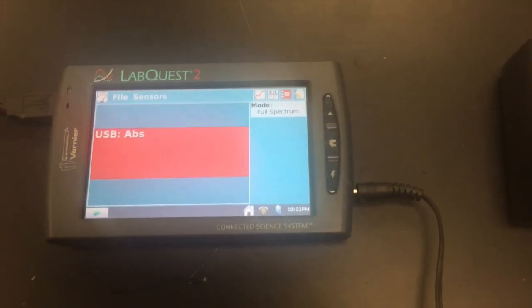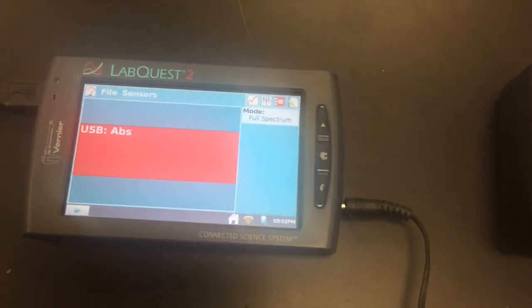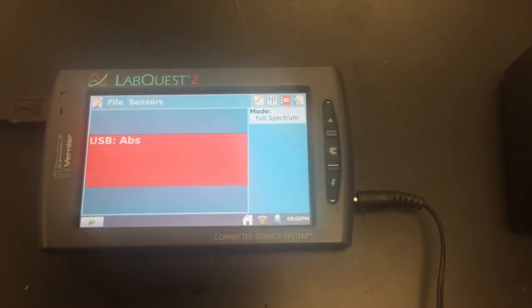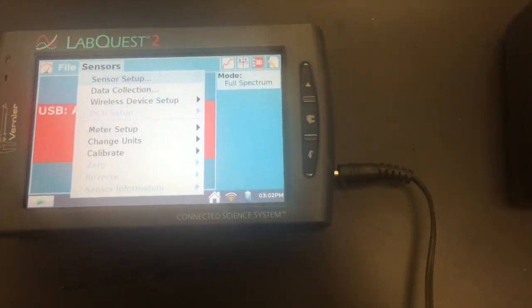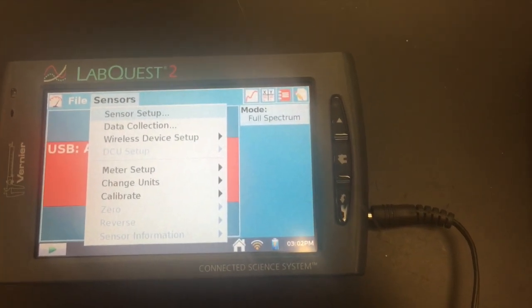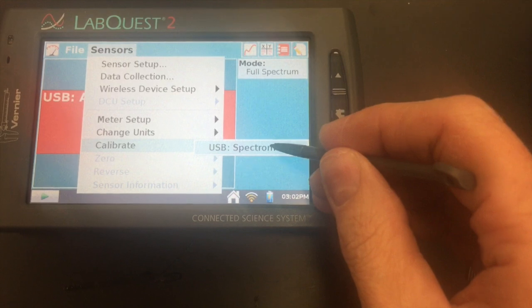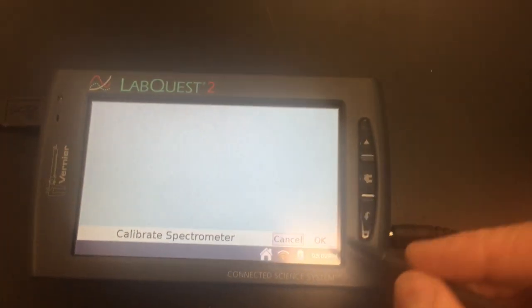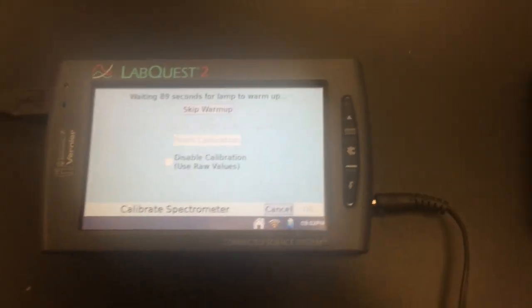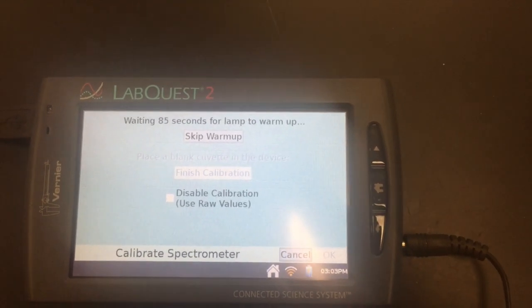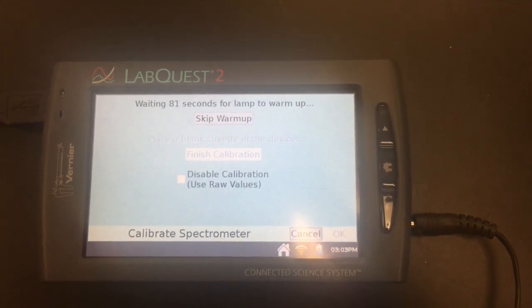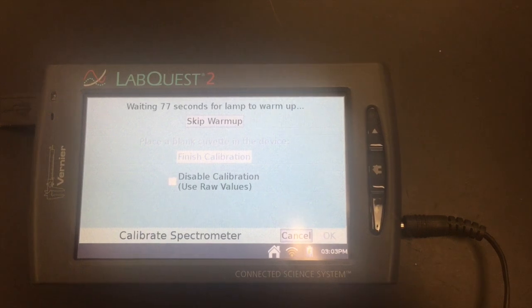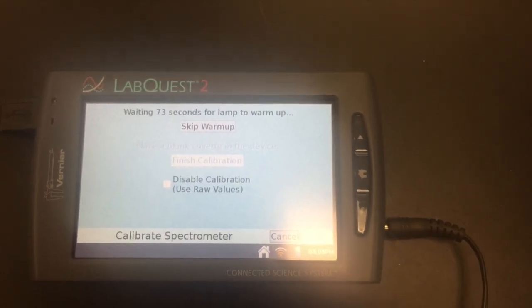Okay, so now we need to tell the LabQuest that we want to zero our spectrophotometer. In order to do that, I'm going to go under the Sensor menu, and you can see that this pops up, and we want to calibrate our spectrophotometer. So I'm going to click Calibrate. It asks, what do you want to calibrate? Well, I want to calibrate my spectrophotometer. The next screen asks if you really want to calibrate that. I say yes. The next screen says you need to wait for 90 seconds for the lamp in the SpectroVis spectrophotometer to warm up. So we're going to pause for a few seconds while we let the light finish warming up.